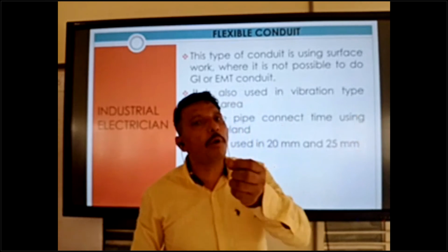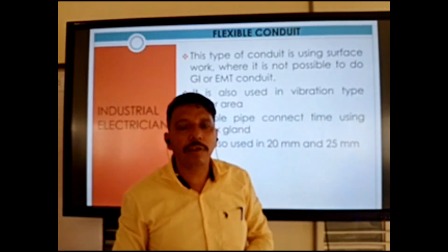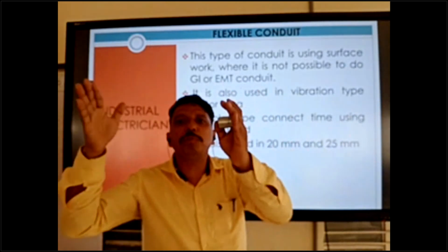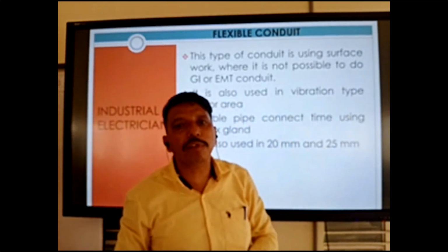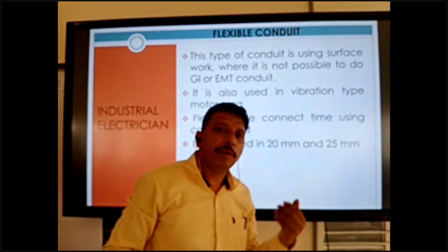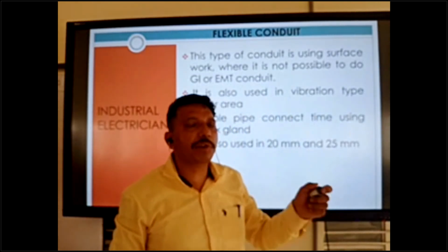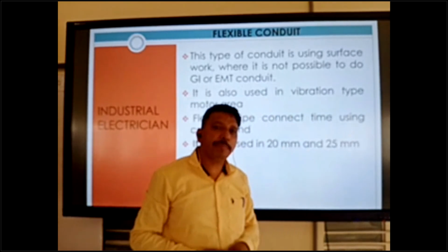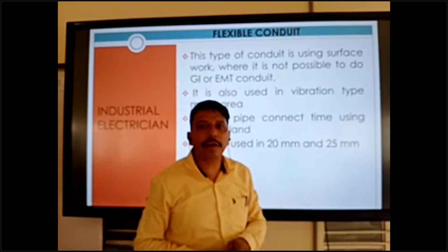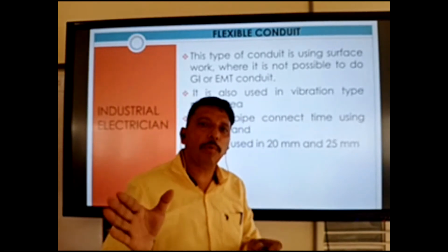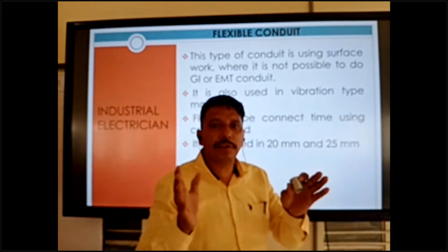So from the DB starting point, do not use flexible. Only in the vibration area, around 1 meter, 2 meter or 3 meters. Maximum 3 meter is allowed. So DB to motor, sometimes your distance is 50 meter, 100 meter, 25 meter, like that. In electrical power supply, the DB to motor distance is like that.